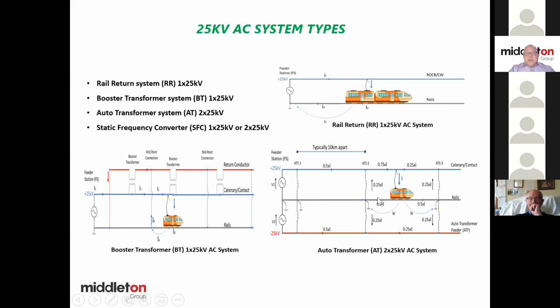So instead of having the series connection of the booster transformer, these auto transformers are connected in shunt. So basically, you are transmitting power to the trains at 50 kV, but your train is still taking 25 kV between the contact wire, the plus 25 kV, and the rails, which is 0 volts in theory. And so the flow of the current is very different.